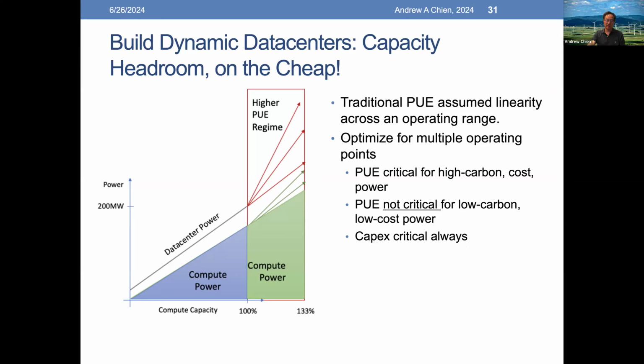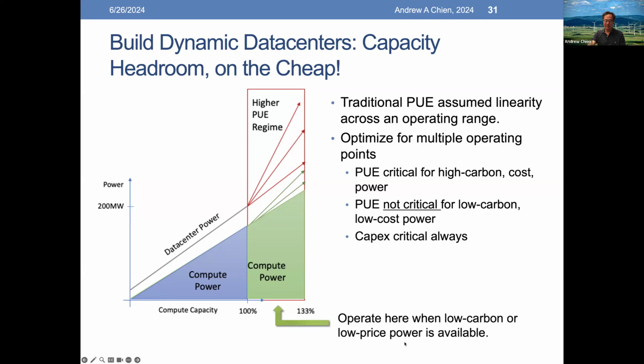So the CapEx is critical always. So the idea is you want to keep the CapEx down, but you want to allow for this PUE to flex so that you can have increased compute capacity when you need it. So the idea here is to operate on this side of the equation when low carbon or low price power is available. And then you're going to wind up operating over here to the left when the power gets really, really expensive.